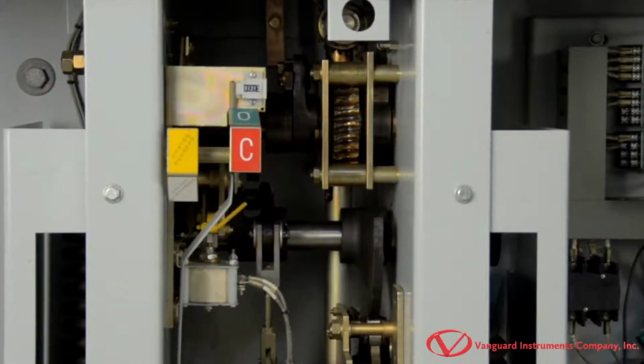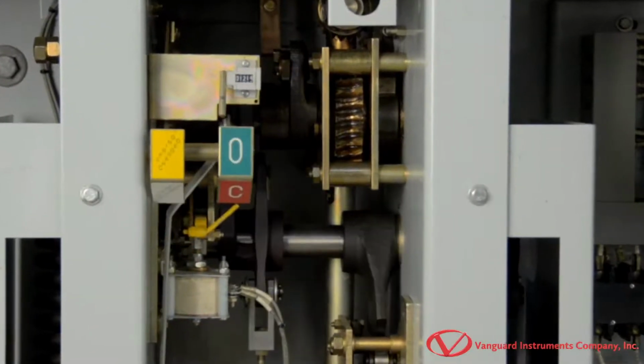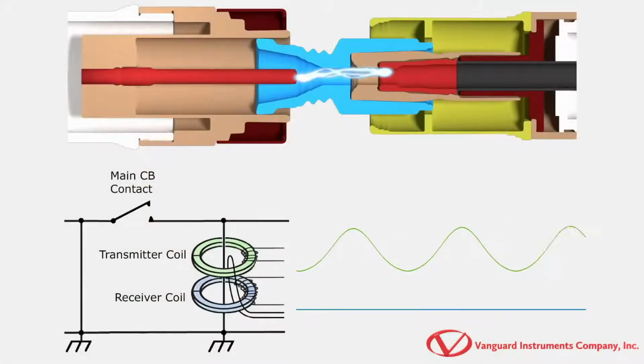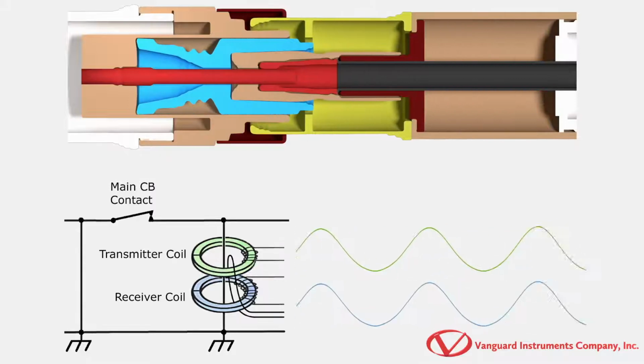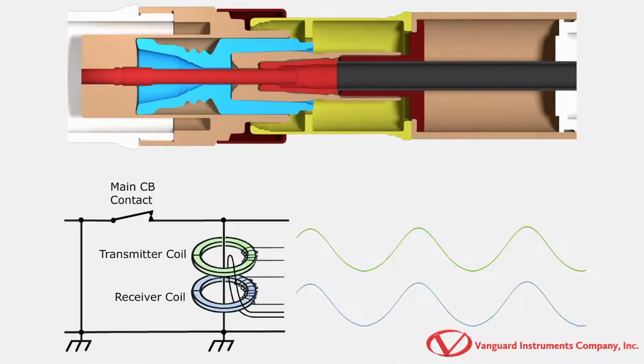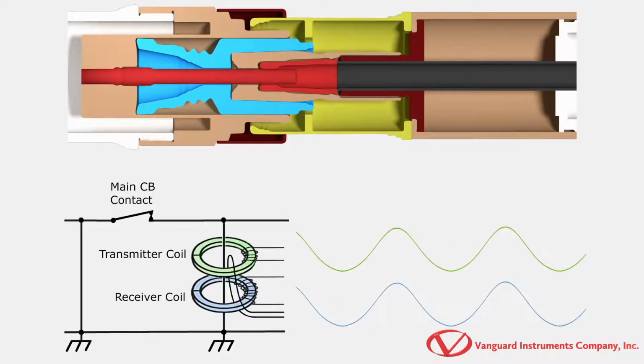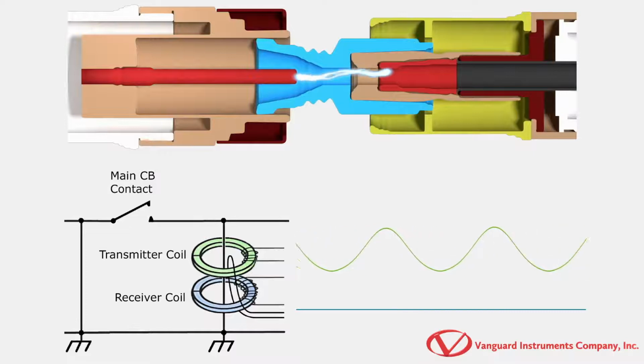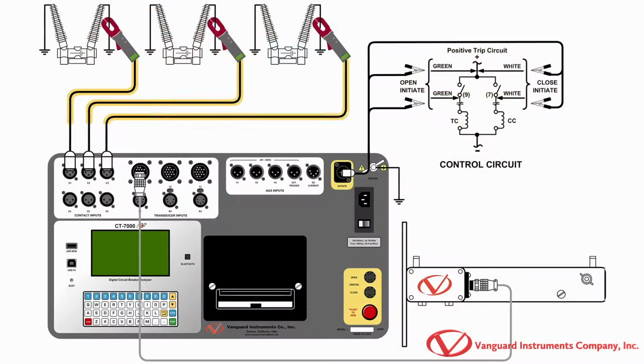Vanguard's timers use a novel patent-pending technique for the open and close timing measurement of the main contacts. With this technique, a high-frequency voltage signal is injected by the transmitter embedded in the measurement probe. If the main contacts are closed, this high-frequency voltage signal will cause high-frequency current to flow through the ground loop and closed circuit breaker main contacts. When the circuit breaker's main contacts open, the closed ground loop is broken and the measurement probe's receiver senses the loss of the current signal. The receiver signals are sent to the Vanguard circuit breaker analyzer, and the algorithm in the unit computes the circuit breaker main contact open and close times.